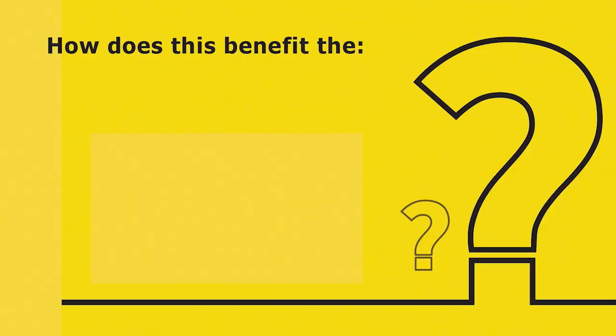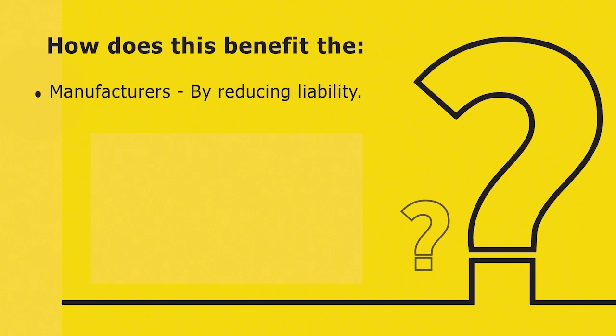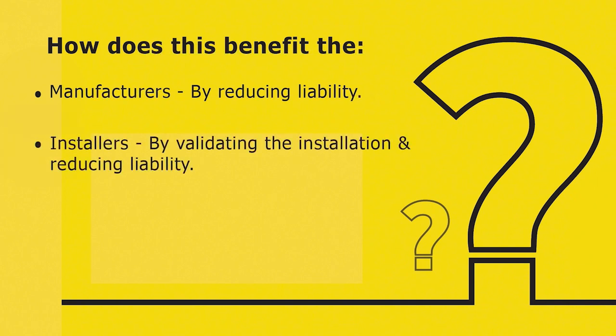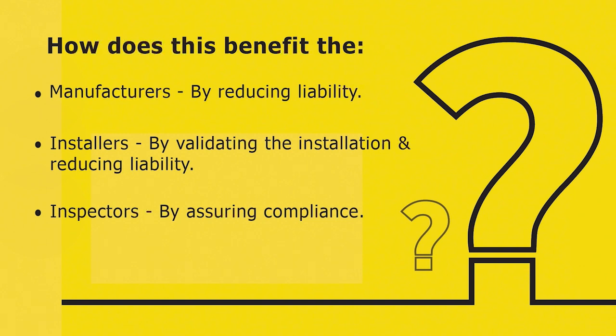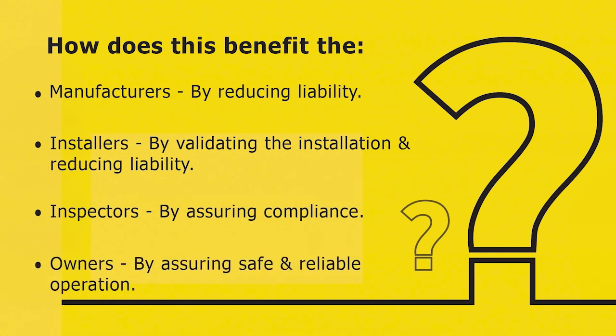So why does all of this benefit the electrical community? Well, it benefits the manufacturers because it reduces liability from construction damage and installation issues. It benefits the installers because it validates your installation and site conditions, and it reduces liability from improper performance. Hey, if you're an inspector or an authority having jurisdiction, it assures proper installation and compliance with Article 230.95. And if you're an owner, it provides you assurance that your system will operate as intended and as designed, and it's really going to reduce the chance of an electrical fire.